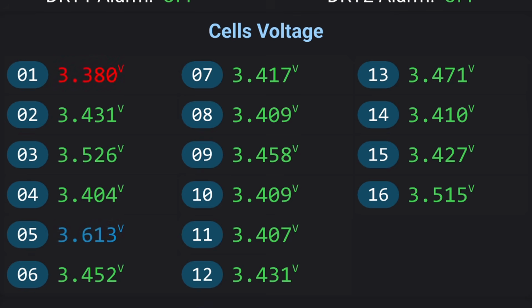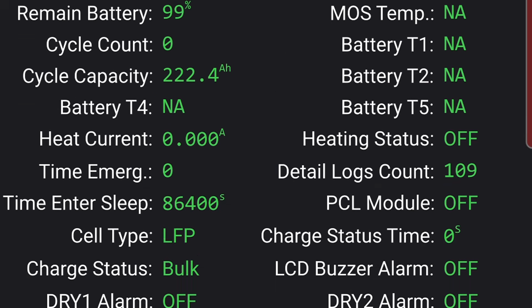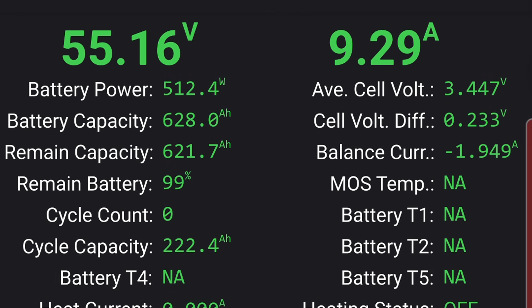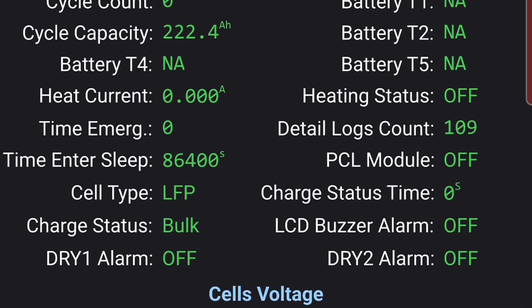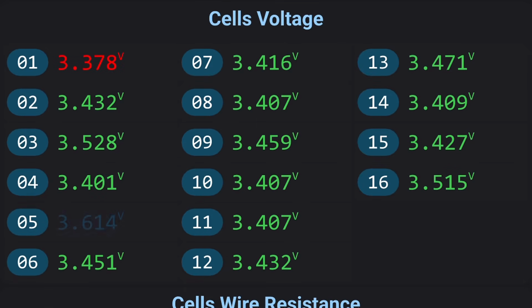Cell number 3 is at 3.5 volts as well. Wow, cell number 5 is climbing. I think we'll see an overvoltage disconnect at some stage with cell number 5, because we are still charging with 9 amps and only balancing with 2 amps. So 7 amps are still going into all these cells, including cell 5, 3 and 16. They will rise in voltage continuously until they hit 3.65, and then the whole charging will stop.